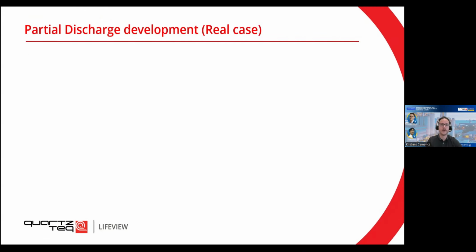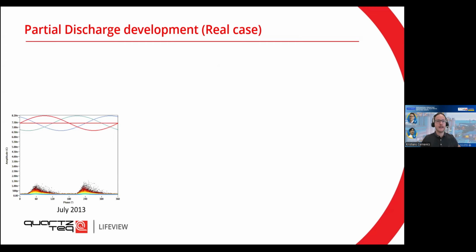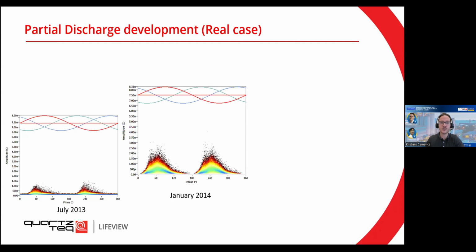And here to show you a real case, this was done with a mobile tool. Essentially, in July 2013, a first measurement was made, and the partial discharge was determined to be somewhere around 1 nanocoulomb. This is still an acceptable level because all machines will have some type of partial discharge. However, what is important is what happened after 6 months. After 6 months, we saw that it increased from 1 nanocoulomb to 2 nanocoulombs. Generally, the rule of thumb is that if your partial discharge value doubles during a year, and this was even shorter than a year, it means you might need to investigate a bit further.